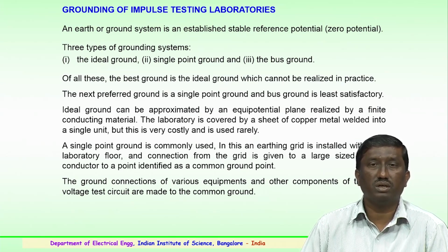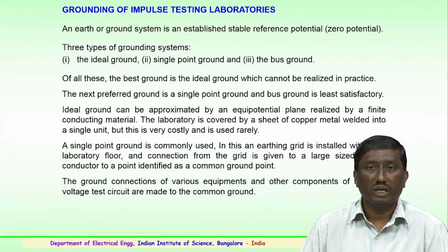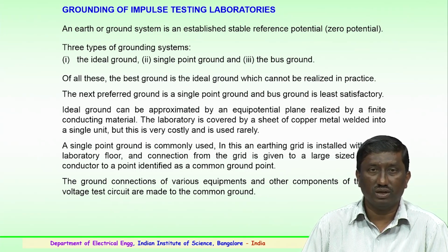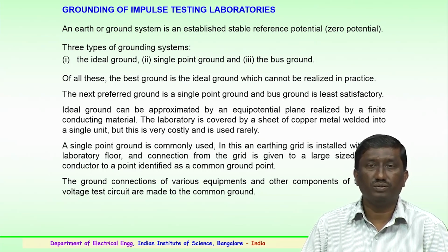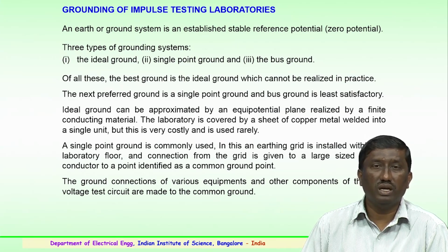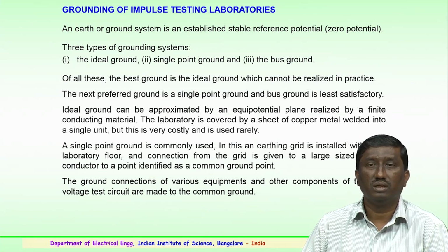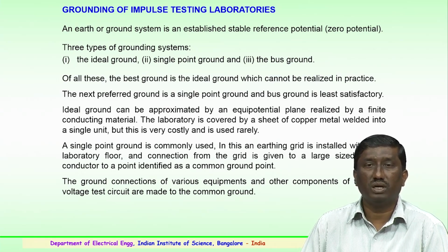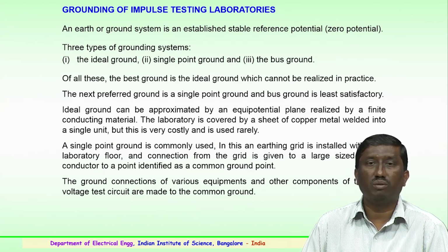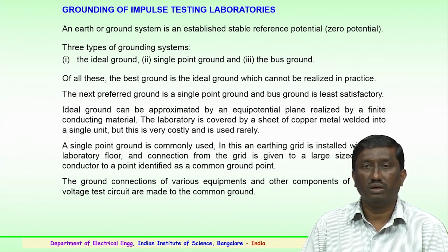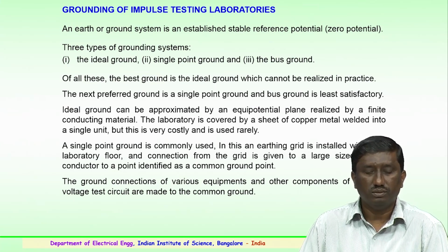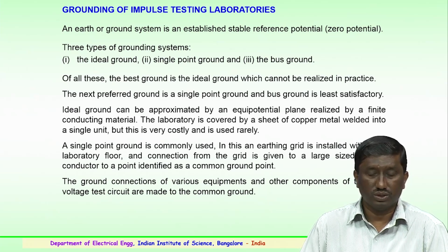Of all these, the best ground is the ideal ground, which cannot be realized in practice, very difficult. The next preferred ground is a single point ground. We will discuss how it looks. And third is the bus ground, which is least satisfactory. So, the ideal ground can be approximated by an equipotential plane realized by a finite conducting material, and the entire laboratory is covered by a sheet of copper metal which is welded into a single unit. But this is very costly and is used in few of the laboratories for few of the equipments to be tested, limited to some tests.